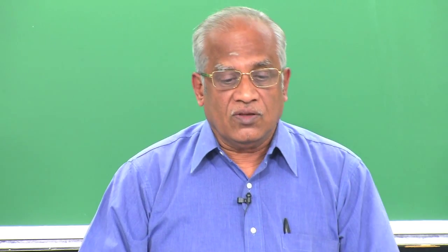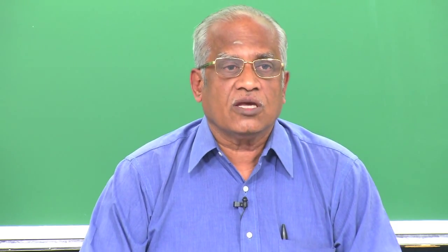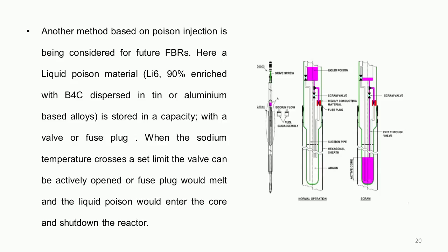Another method is based on poison injection, similar to thermal reactors. For instance, a liquid poison system uses lithium-6 as poison along with boron carbide, put in a tin or aluminum-based alloy with a fuse plug. This fuse plug melts when sodium crosses a particular temperature. However, there is still a need to determine how to remove this poison from the sodium afterward — this area needs more work.